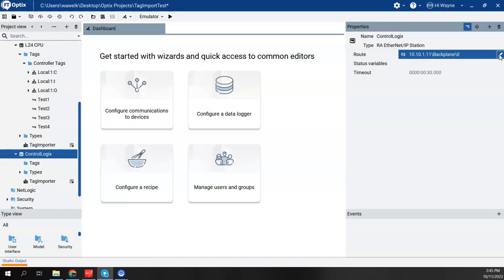Now again, if I'm bridging through an Ethernet module to get to the CPU, if I just gave it the IP address without the backslash backplane backslash 0 or the slot, then it's not going to connect. It's not going to find the tags. It's not going to allow you to import. So this route, this syntax, is very important when we're bridging through an Ethernet module.